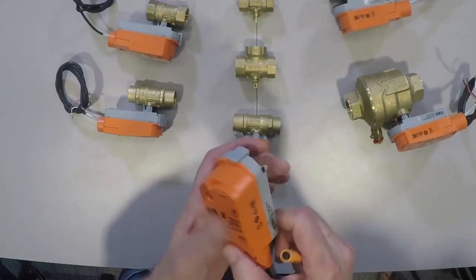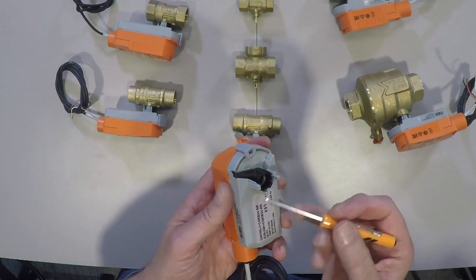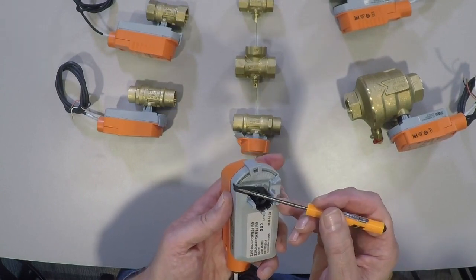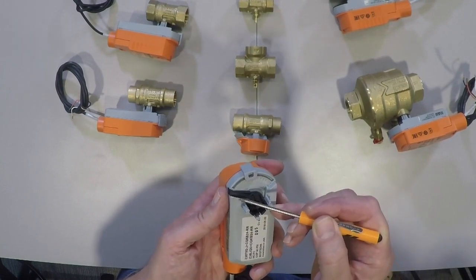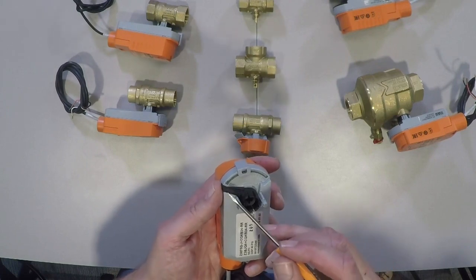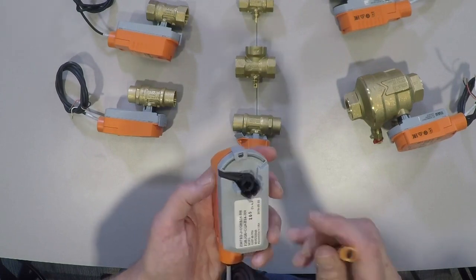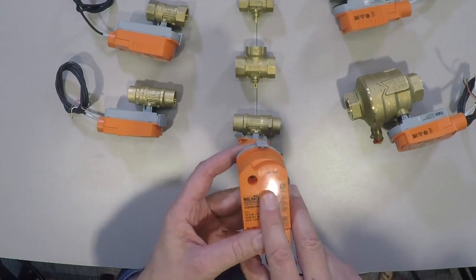The valve will go through a full cycle from closed to full open, and it'll go back to closed, whatever the starting position was. The reason is the actuator has to know for its memory what it considers to be full open or full closed.